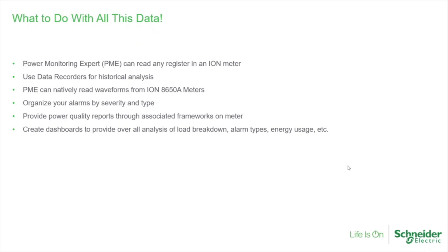And it also supports different reports. Our meters support a 4-30 report. It's a general PQ report. It's looking at voltage, frequency, your THD values, and has some swell events recorded in there. And then we have a 519 report that's specifically looking at harmonics and is making sure that they're not exceeding the recommended thresholds per the 519 standard. And then there's also an EN 50160 report that's supporting our meters. That's a European report, so I haven't seen a lot of US customers use it, but it's available.